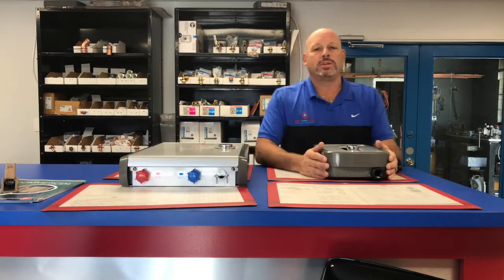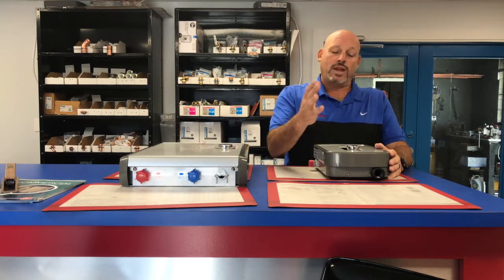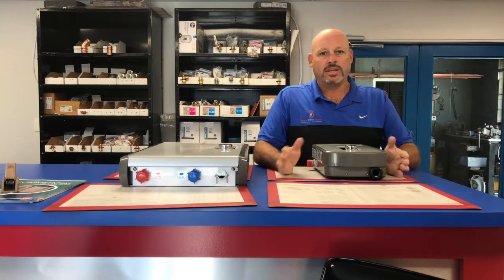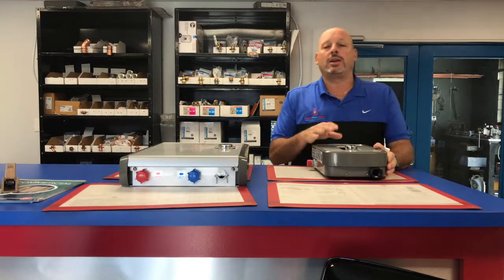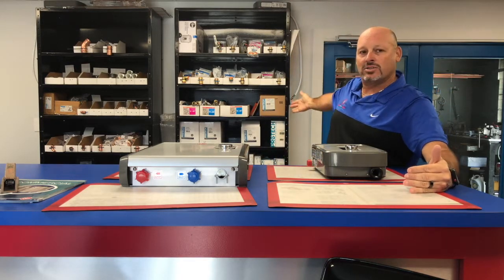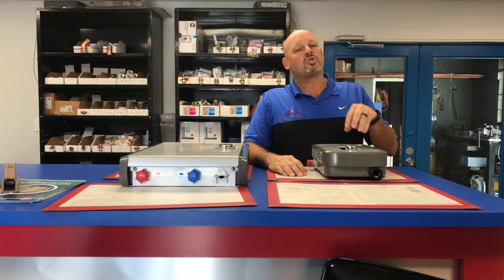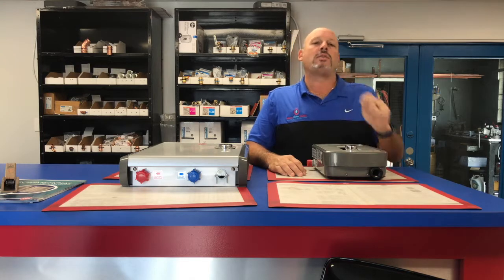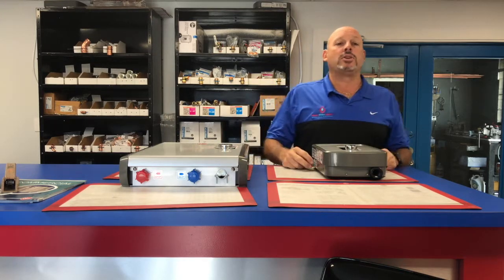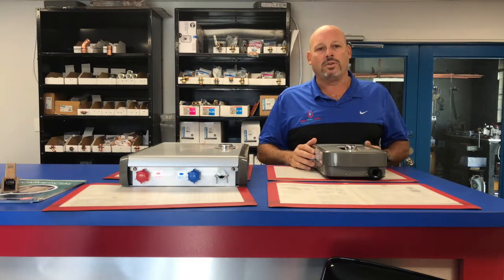One of the problems you run into with this heater in an apartment building: most apartment buildings have 150-amp service. If your AC uses 50 amps and the water heater takes 60, that leaves you only 40 amps for the whole rest of your apartment — that's not enough. Another downside in an apartment: even if your water heater is in the closet and the breaker box is right across the hall, number 6 wire is three times as fat as number 12 wire and will not fit through the conduit you have. You'd have to break walls to get it in — that requires an electrician. Also, you need a minimum 200-amp service; if you don't have that, this isn't going to work for you.